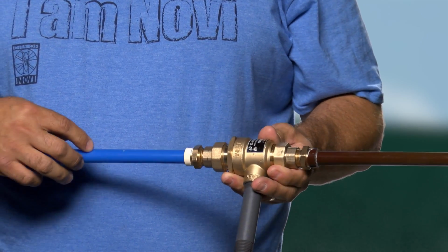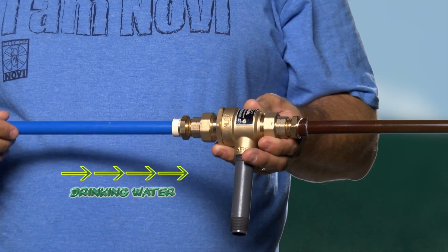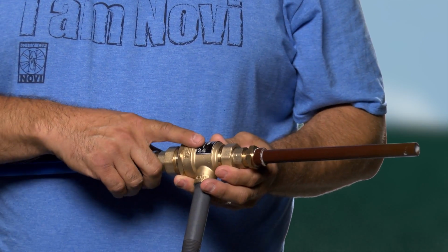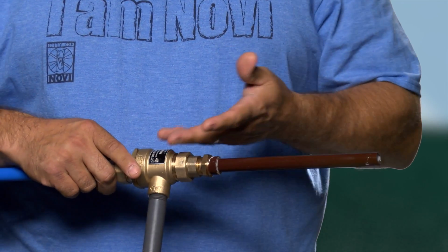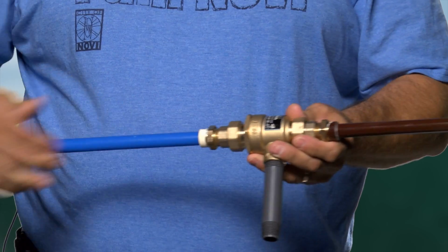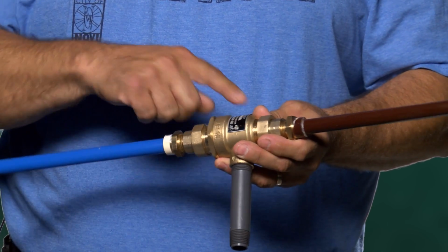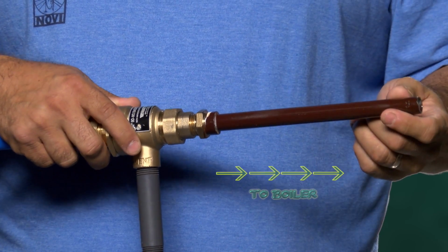And what you see here is the blue represents the water flow that comes from your home, your drinking water supply, that flows into this device. And then it feeds, and for this device, it would feed your boiler system that does not have a chemical additive, because this is a low hazard device, and if you have a chemical additive in a boiler, that gets you into a different type of assembly that's more of a high hazard. But the water flows in here, what the blue is representing, it goes through the device, and it goes to the piece of equipment, and in this case, a boiler.